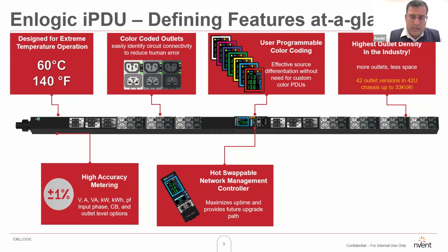The network management controller, which is the heart of the PDU and offers the intelligence, is hot swappable. This means you do not need to power off the PDU or your servers when you need to replace the NMC. We don't expect the NMC to fail very regularly, but it's a proven fact that if there is any point of failure in a PDU, it's usually the NMC because of the electronics involved. Because it's hot swappable, you have no reason to shut down your PDU or have any downtime in your data center.